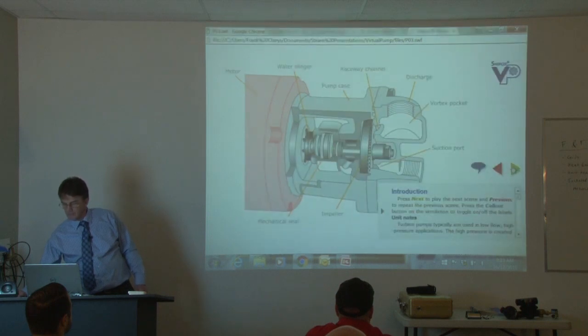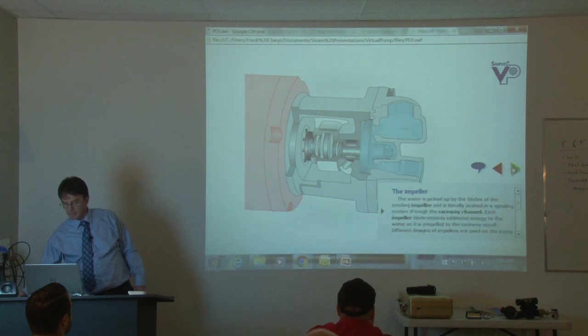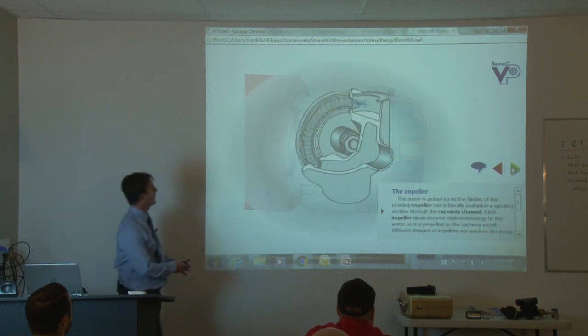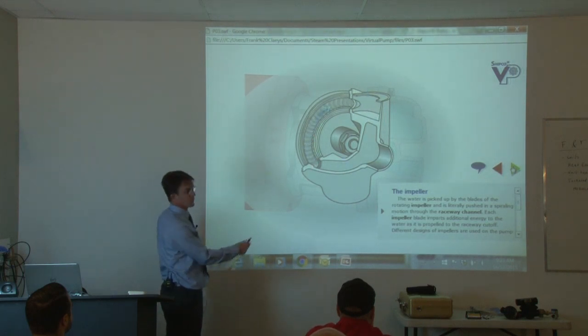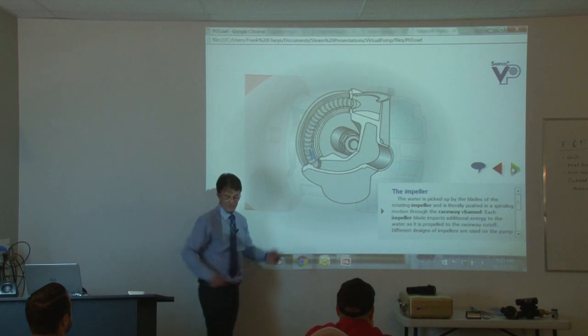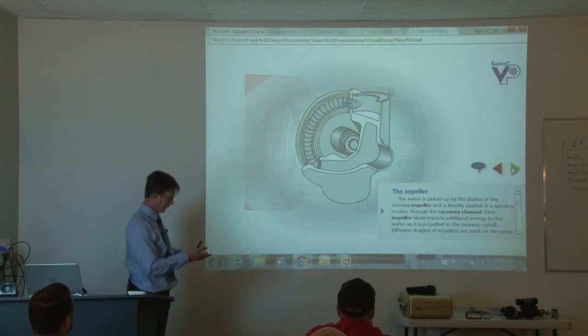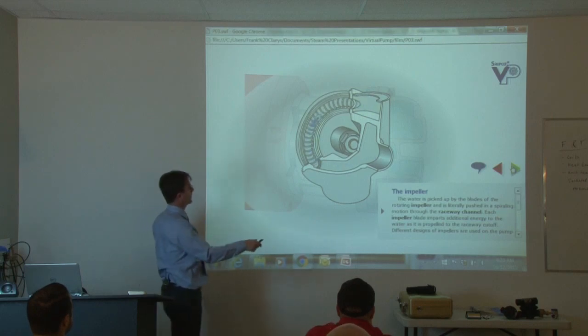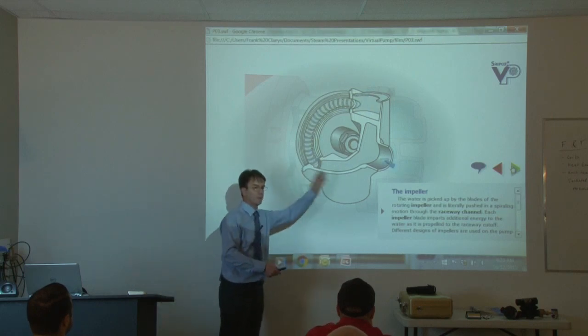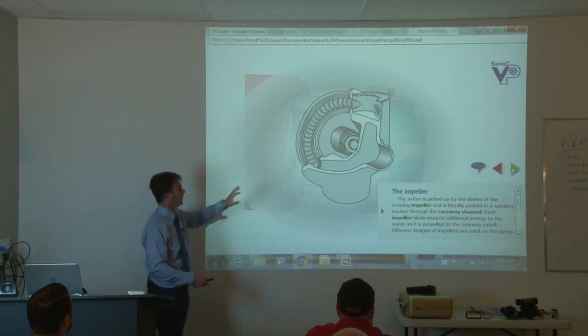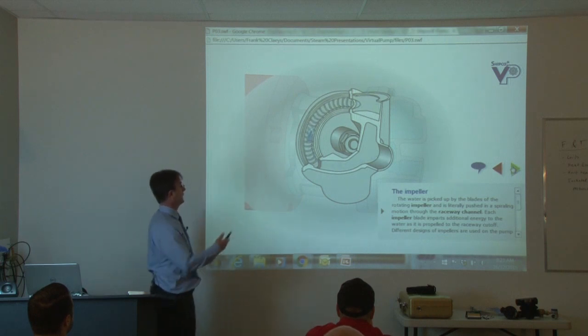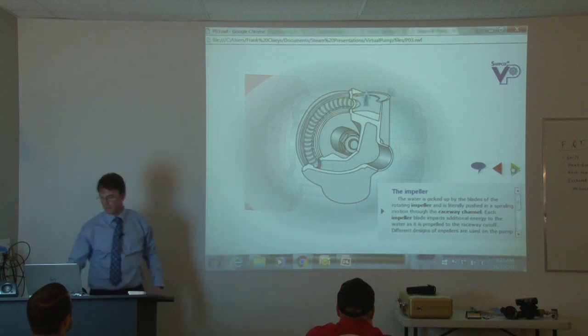The turbine pump operates in a similar way, but the big difference is that all the little vanes are much closer together - you can't even get your fingernail in between the vanes. So if it's a turbine pump, you need a strainer upstream. If it's a regular centrifugal pump, a strainer is not required and not even recommended. Some people still have a preference for them.